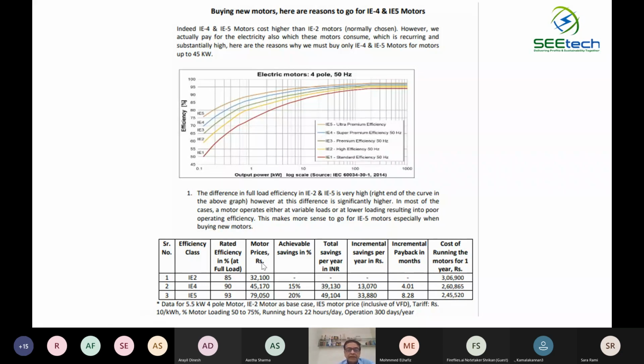But friends, see the difference here. The operating cost of that motor, if you are going to buy an IE2 motor, is going to cost you around 3 lakh, whereas with IE5 it is going to cost you around 2.45 lakh only. So whatever is the incremental additional amount you are paying, that is 79,000 minus 32,000, that is going to get paid back to you in so little time, that is 4 to 8 months. So learning number one: the cost is not in the appliance, or in the purchase of an energy consuming equipment. The real cost is in consuming it.